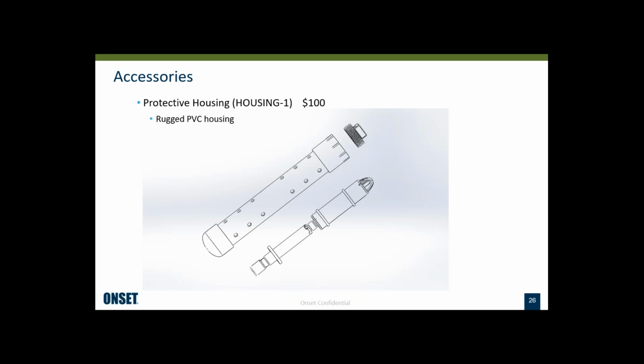Another accessory that they may want to consider is a protective housing for their MX801 logger. It's designed to be big enough to hold the logger and any of the sensors, including the DO sensor, and it includes a couple of grommets to hold the logger in place, as well as a grommet for holding the sensor in place within the housing. So it makes a nice, very robust housing for the logger for those underwater deployments.